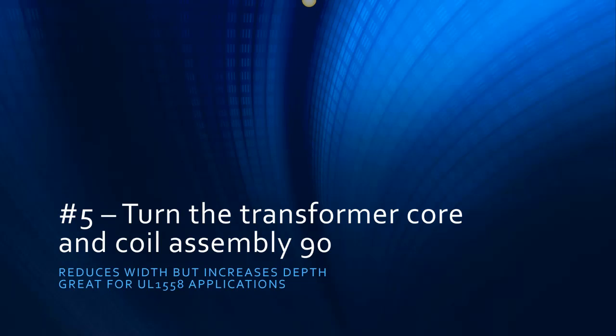So we've had customers come to us and say, I need absolutely every inch of room that I can get in the electrical room. I need to reduce the size of this e-house, that kind of thing. So we turn the transformer core and coil 90 degrees. Now it's ABC front to rear. And we put the temperature controls, of course, still on the new front of the transformer.